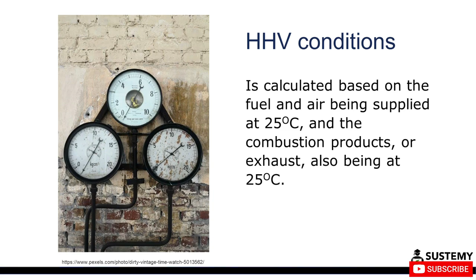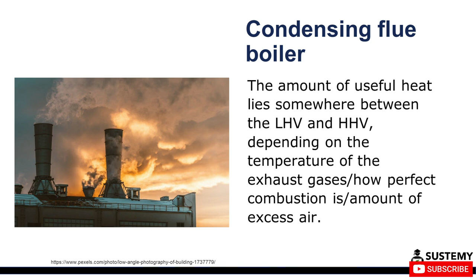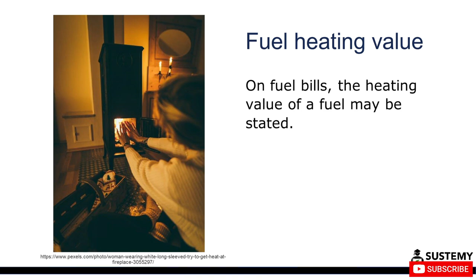Now, some manufacturers of condensing flue boilers claim an efficiency of greater than 100%. This is, of course, impossible based on the first law of thermodynamics. When claiming this, they have used the LHV, or the lower heating value, when calculating the energy input. In a condensing flue boiler, the amount of useful heat out is somewhere between the LHV and the HHV, depending on the temperature of the exhaust gases and the extent to which combustion is perfect and the amount of excess air is low. On fuel bills, the heating value of a fuel may be stated.